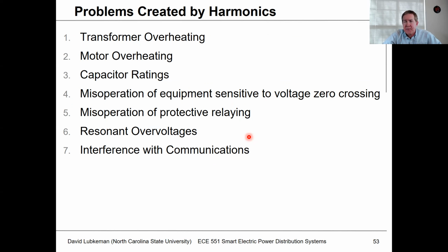So there's usually a derating factor you'd have to supply, or you'd have to come up with, where you can't load your transformer up as much. You'd actually have to back off on how much loading you put on if it had a lot of harmonic content. As I mentioned before, this is going to overheat motors. And so this is why we're careful in industrial situations not to have too much harmonic in the voltage supply. It affects capacitor ratings because capacitors sink harmonics.